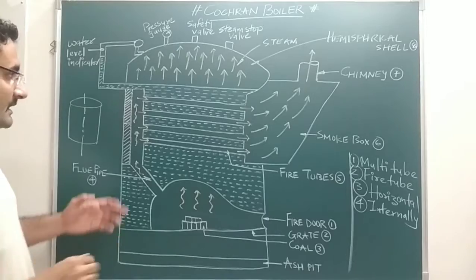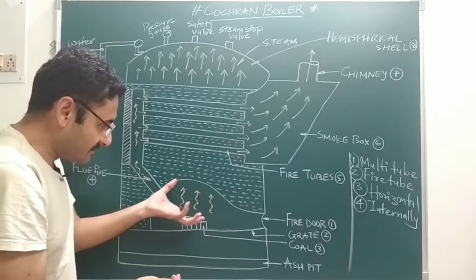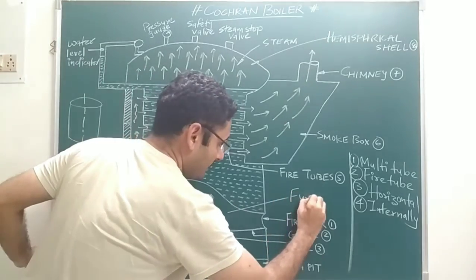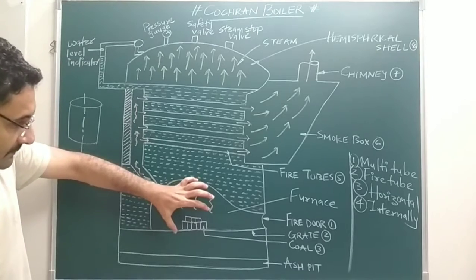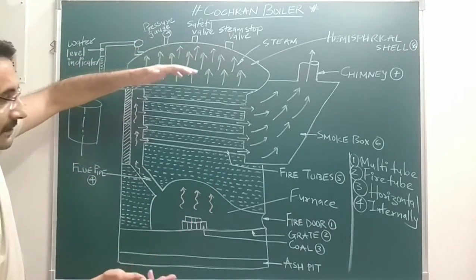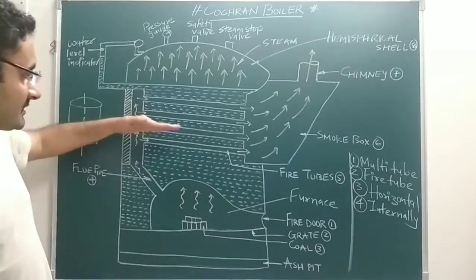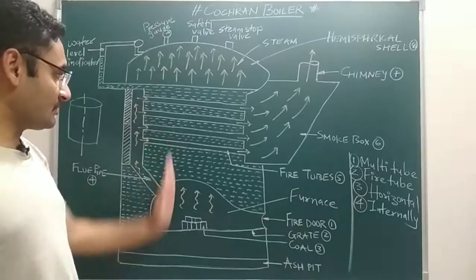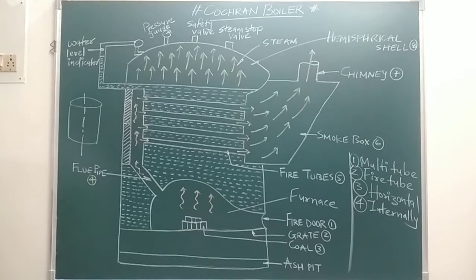Next point: it is also known as an internally fired boiler. It is called internally fired because inside the shell of the boiler, there is a furnace, and inside that furnace, combustion is taking place. Since the furnace is present inside the shell, combustion takes place inside the shell — that is why it is known as an internally fired boiler. So the four basic characteristics are: multi-tube, fire tube, horizontal axis, and internally fired boiler.